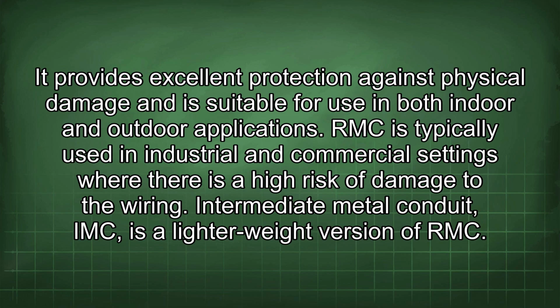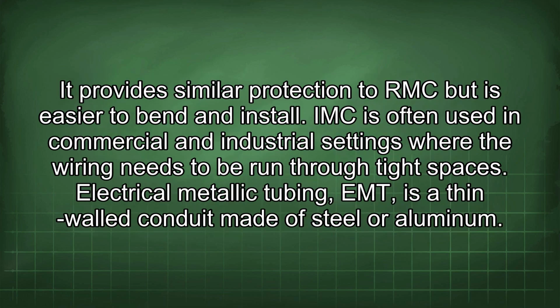RMC is typically used in industrial and commercial settings where there is a high risk of damage to the wiring. Intermediate metal conduit, IMC, is a lighter weight version of RMC. It provides similar protection to RMC but is easier to bend and install. IMC is often used in commercial and industrial settings where the wiring needs to be run through tight spaces.